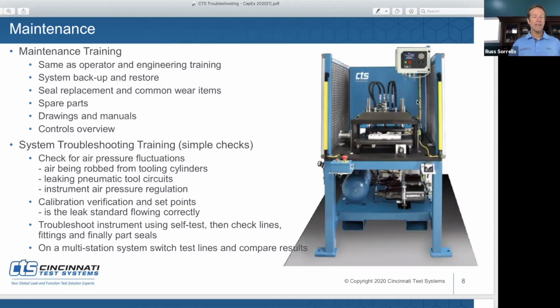And it was just blowing my mind. The instrument was fine. I did the self-test, all of that, just searched and searched. I mean, soapy water, every fitting, everything. There was nothing leaking. And finally I had sprayed so much soapy water that it began to run over the side of the fixture and off the tooling plate and onto the actual table. And I hit the start button one time and I saw air coming from between the tooling plate and the table that it was actually sitting on.